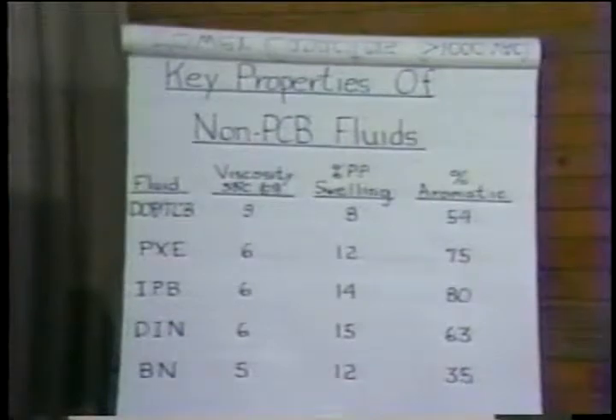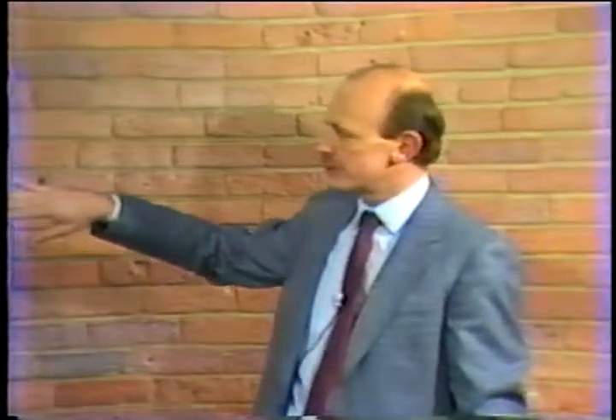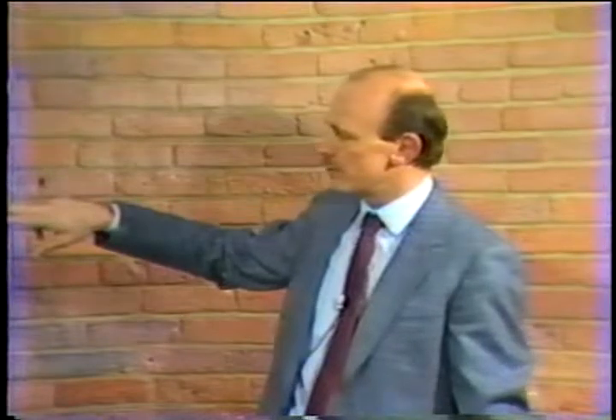To do that, the fluid must have a very low viscosity. Also, it's important that it doesn't swell the polypropylene film very much, because if it swells the film, it can close up those important spaces between the film and the foil. Another factor that involves the chemistry of the fluid is the percent aromaticity. By the aromatic content, I mean the percentage of the number of carbon atoms that participate in aromatic double bonds. So now we find that the percent aromaticity is a very important parameter because it affects the gas absorption of the fluid.